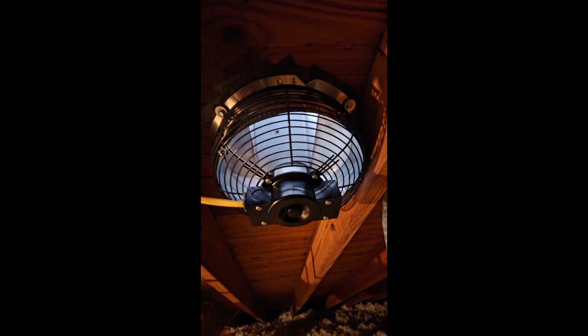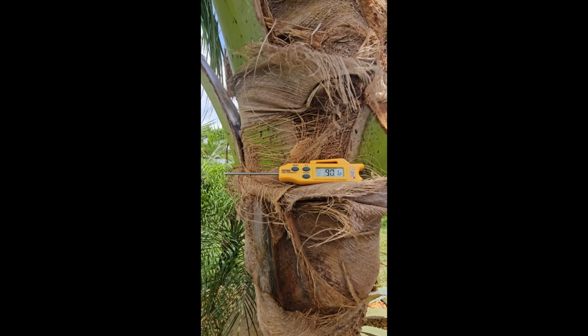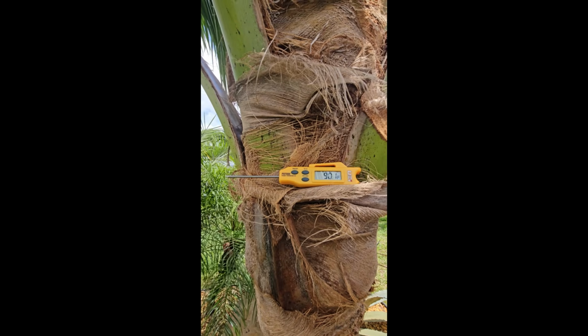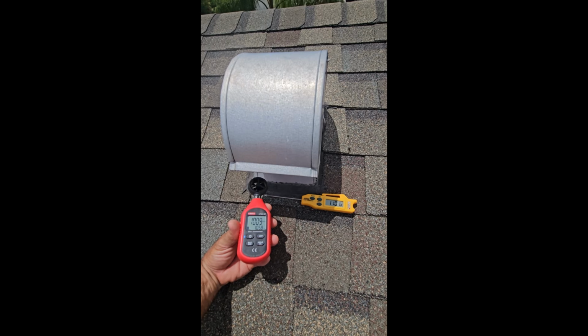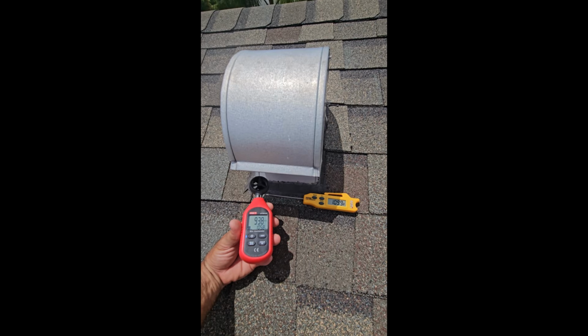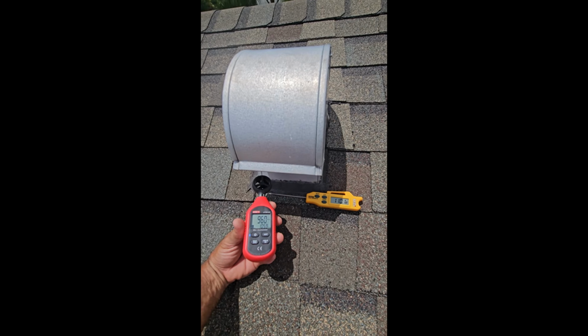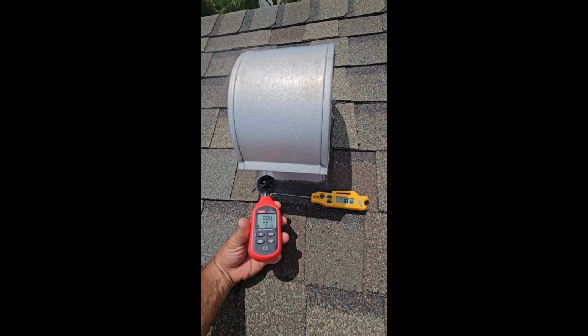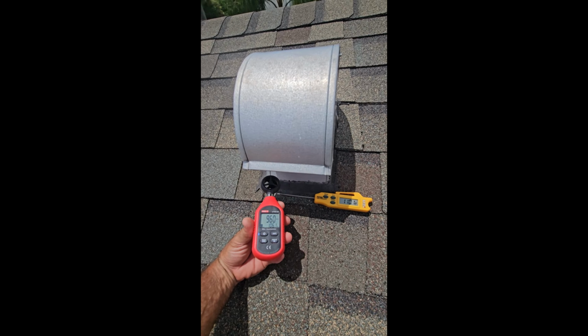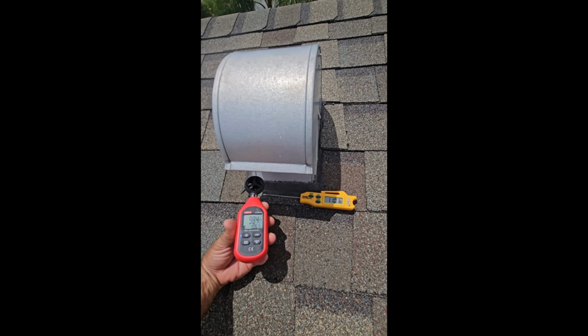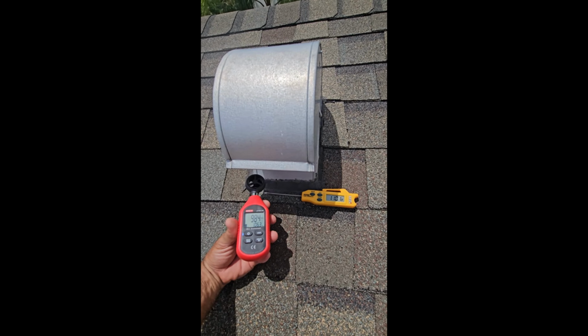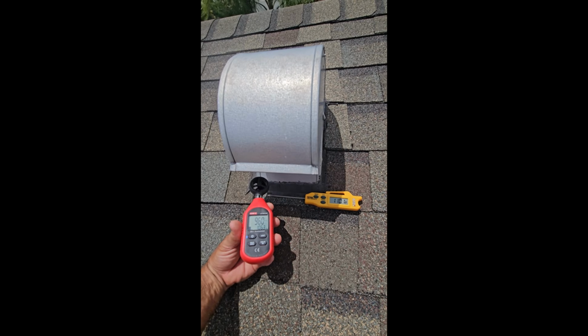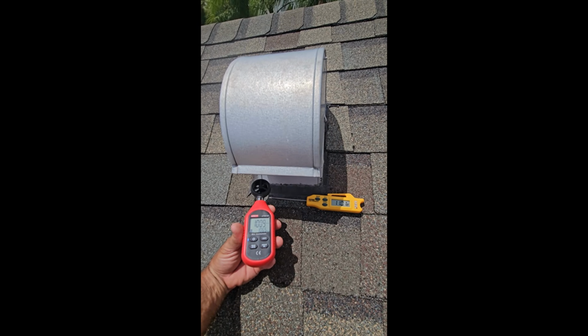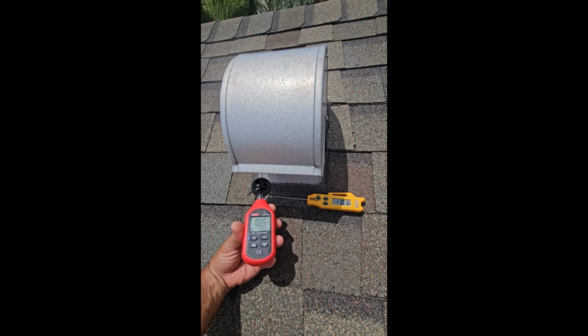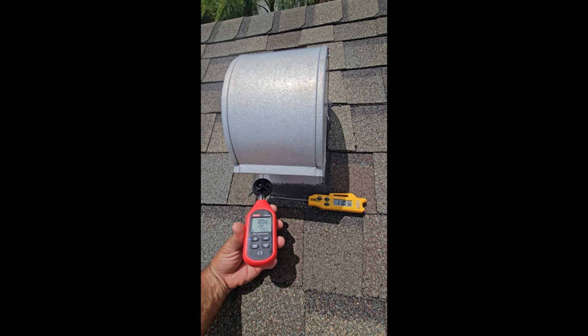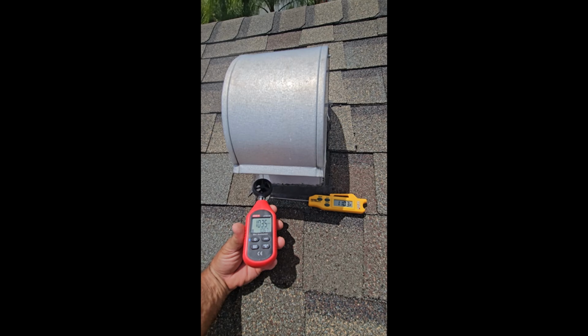Okay, let's go on the roof and take a look at the flow rate coming out of the gooseneck. The temperature in the shade is 90 degrees. Okay guys, you can see it's over 1,000 feet per minute coming out of this vent now. It's showing right around 106 degrees on the unit. You don't want to look at that one because it's an internal sensor. The one on the right, you can see the yellow one is 110, the air coming out of the attic. So a big difference from the outside temperature, pulling out that hot air at a very good rate of over 1,000 feet per minute compared to before, which was virtually nothing.